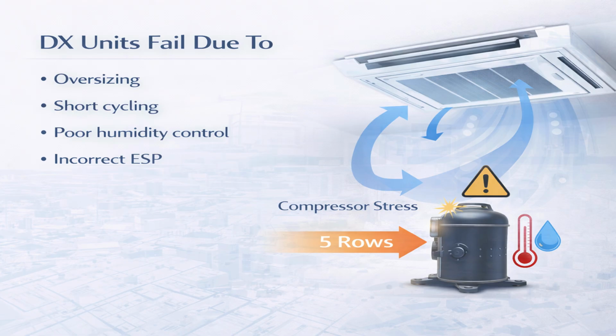When a DX unit is oversized, it cools the space too quickly and shuts off before it has time to remove sufficient moisture. This short cycling reduces dehumidification, increases power consumption due to frequent starts, and places repeated mechanical and electrical stress on the compressor. Over time, this leads to higher energy bills, unstable comfort, and premature equipment failure.